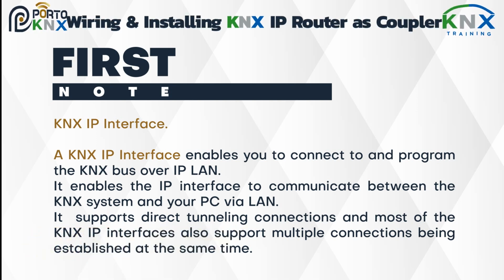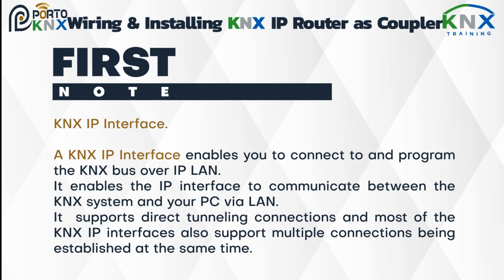KNX IP interface. A KNX IP interface enables you to connect to and program the KNX bus over IP LAN. It enables the IP interface to communicate between the KNX system and your PC via LAN. It supports direct tunneling connections, and most of the KNX IP interfaces also support multiple connections being established at the same time.